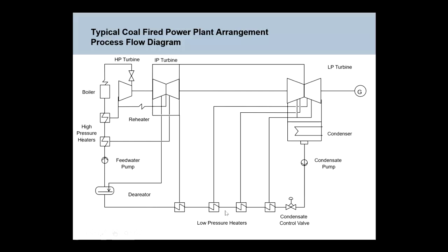So these things are feed water heaters, through a deaerator, which is heating the water as well. Another pump, a feed pump, to get hot, really high pressure water through some high pressure heaters, back into the boiler where it's boiled, made steam, and around the cycle again. Okay? So that's a very quick run through a steam cycle. A couple of things to note.